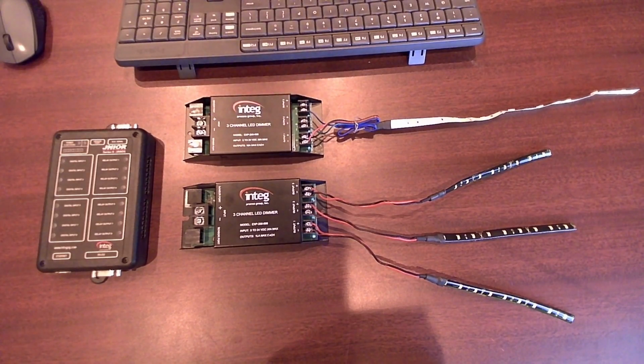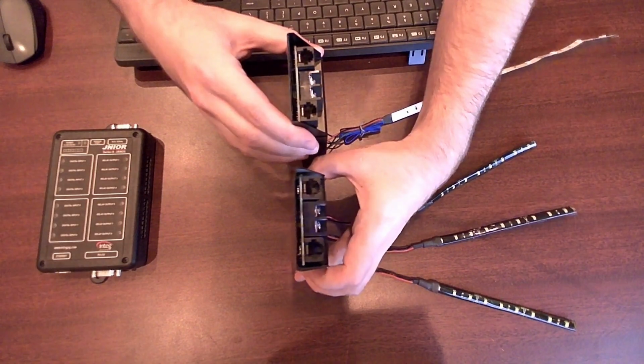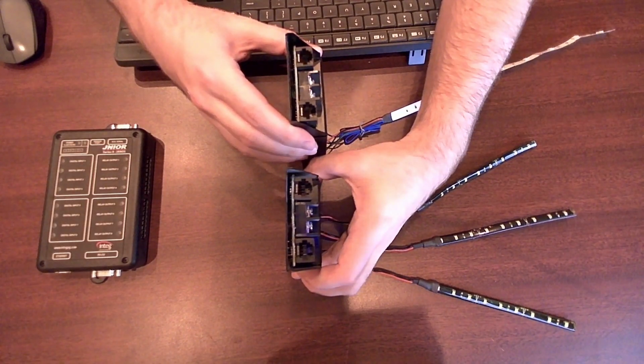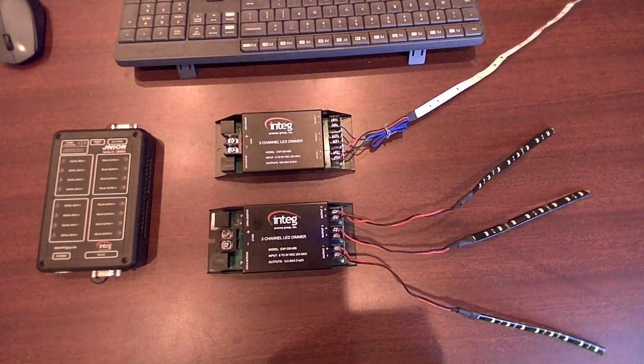Each output on a 3-channel LED dimmer can handle up to 10 amps and provides pulse width modulated control that can regulate LED strip lights from 0 to 100%. Wiring a single output to an LED strip can give it control over one color, while wiring multiple outputs to a single LED can give it control over multiple colors. Looking at the sides of the 3-channel LED dimmers, you'll see that each one has 2 female connectors for sensor ports. This allows you to daisy chain multiple expansion modules with these 3-channel LED dimmers.